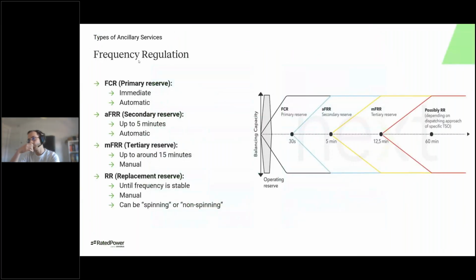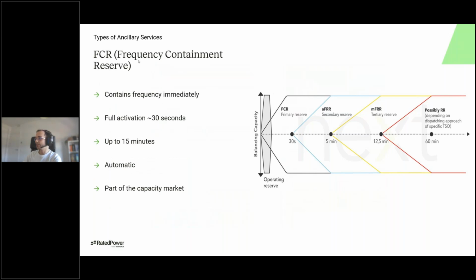And I would like to focus primarily on frequency regulation because it's the primary use case for batteries. And here we have four, well, according to ENTSO-E, we have four definitions. We have primary reserves, or FCR, secondary reserve, or FRR, a tertiary reserve or manual FRR, and replacement reserve. And I will go a bit into detail now. So the first one, the primary reserve, is the frequency containment reserve, according to ENTSO-E.